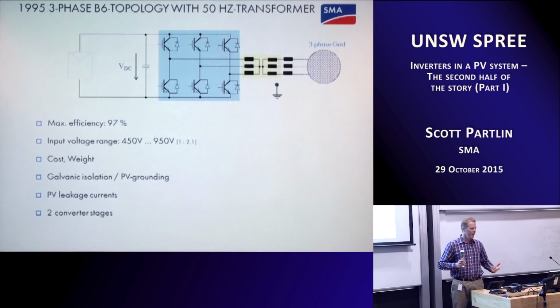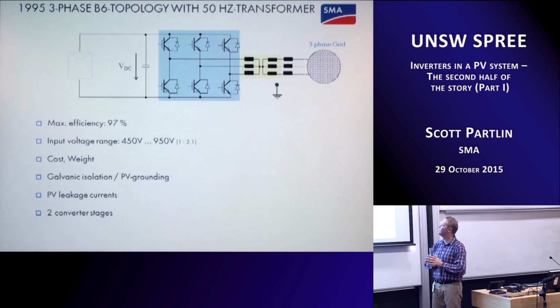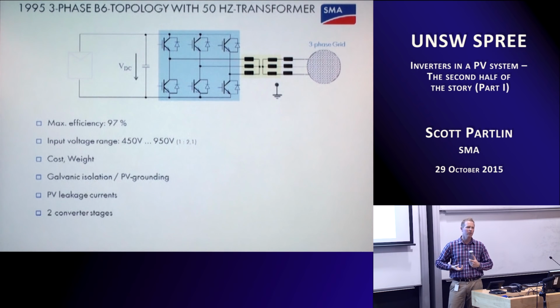And then the other technology is three-phase technology. Most businesses will operate on three-phase power. A lot of homes will operate on single-phase power, so all of those previous classes of inverters are suitable for them. But when you move into, say, a commercial system, so there's a large PV system on the roof of this building, that's a three-phase connected system. It needs to rely on a different technology to the single phase, or you need to duplicate 3 inverters, one for each phase, which means less reliability, more components, more cost.